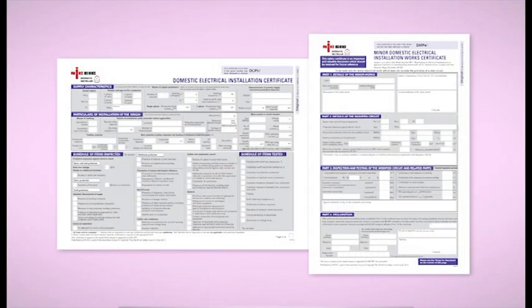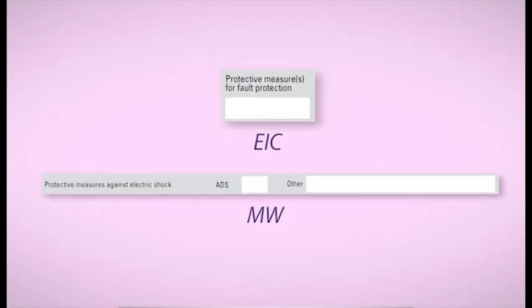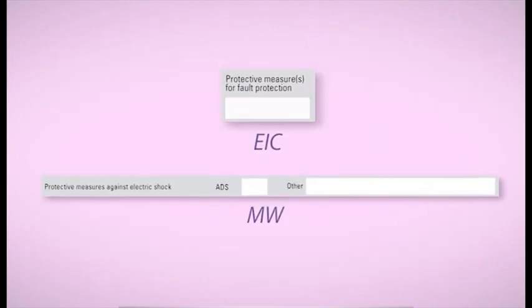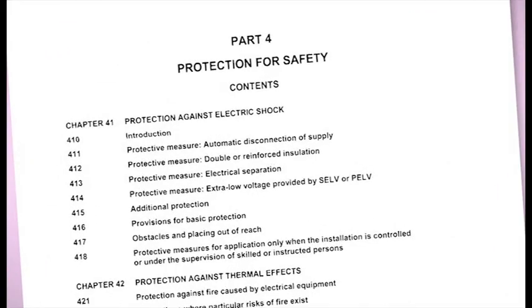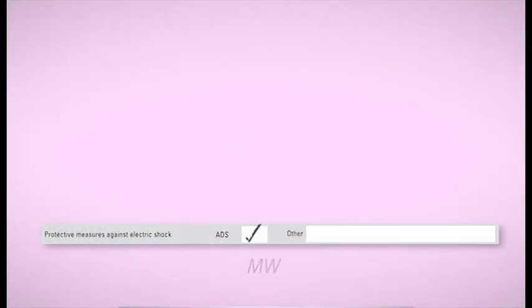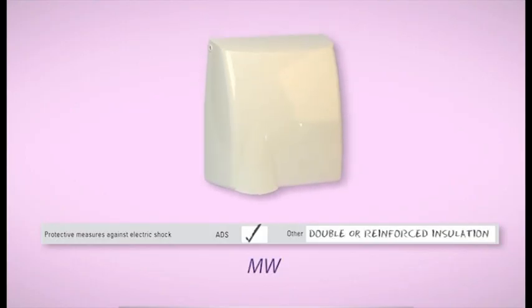The next box to examine on the certificates deals with protective measures for electric shock. Now this in most cases is automatic disconnection of supply, ADS, but can be followed by one or more of the protective measures detailed in Chapter 41 of the regs. So for example, double or reinforced insulation could be recorded for a circuit supplying a non-metallic hand dryer, which is a common example of equipment adopting this protective measure.